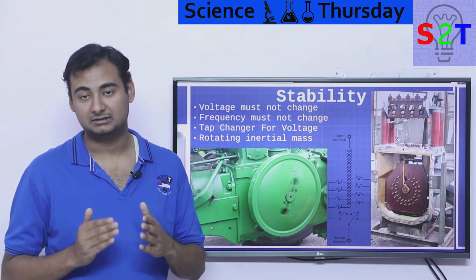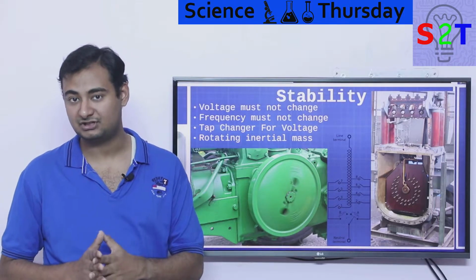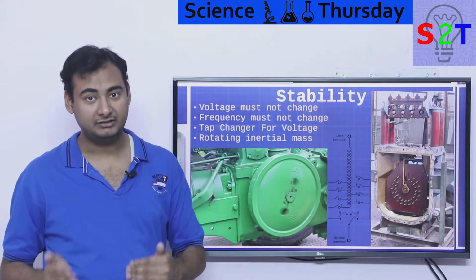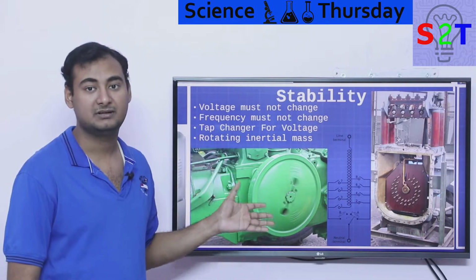So this is how we handle it. Voltage is handled at the substation level using a tap changer. The frequency, which must not change, is taken care of by the spinning mass.